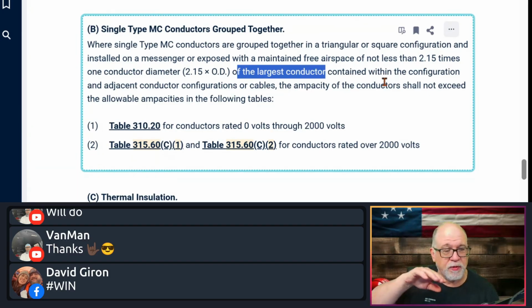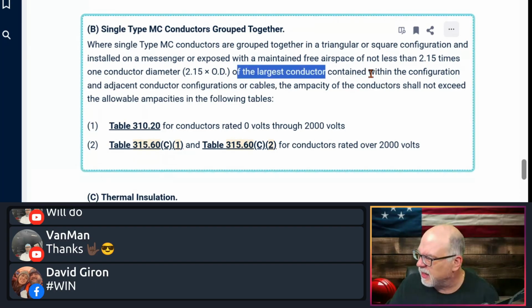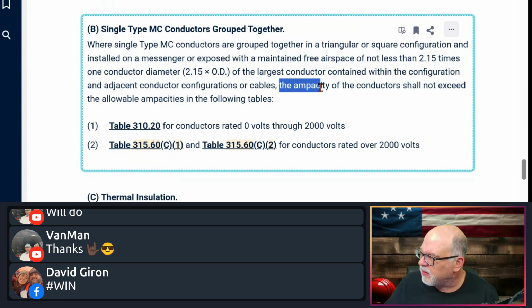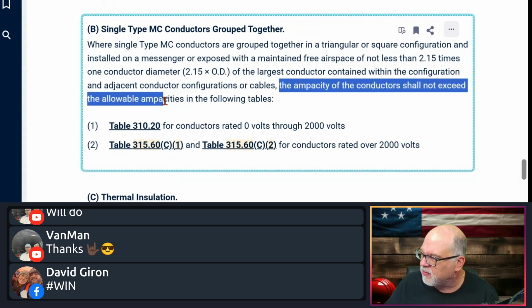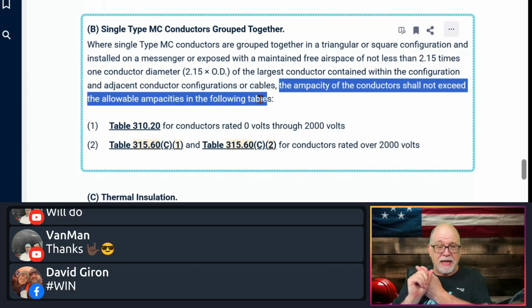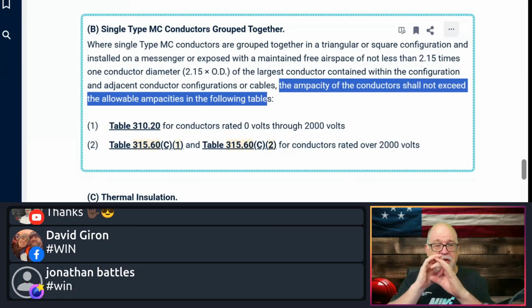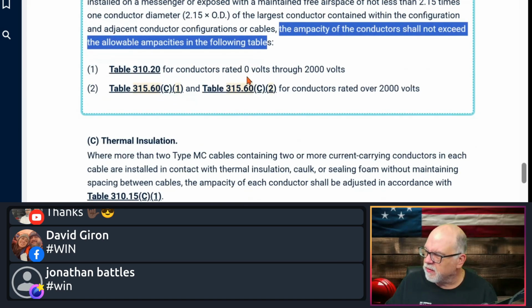Okay. Maybe I'm doing all 250 kcmils. I just take one of them, that type of thing. Okay. Contained in the configuration and adjacent conductors, configuration or cable. The ampacity of the conductors shall not exceed the allowable ampacities in the following tables. This is not brain surgery. So if you're running a system where you're on a messenger or you're exposed in a maintained free airspace because of your spacing, and you're going to be putting them in a triad or in a quad or a square configuration, and you maintain spacing, all it's saying is the ampacity of those conductors have to meet these rules: 310.20 or 315.60. This is for medium voltage.